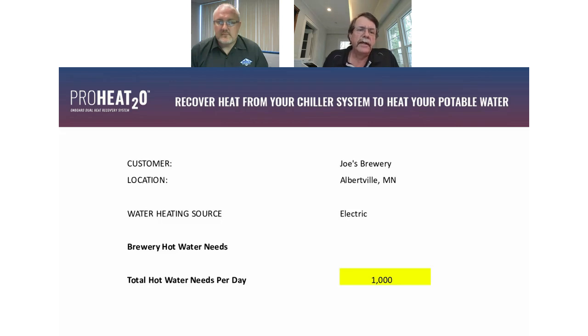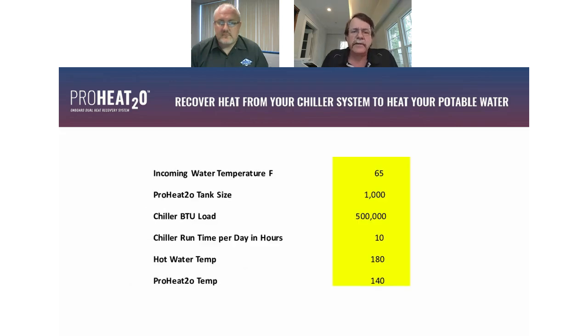So a big thing to consider that we many times don't consider is what the incoming water supply is. If you're located in Phoenix, Arizona in the summertime, a city water tap will often be 90 plus degrees. That's a big negative when it comes to cooling things, but it's a big positive when it comes to heating your water source. Some of you in the upper Midwest that are on a well system, it's not uncommon to have 55-degree water. That's a greater load on your heating system to create hot water.